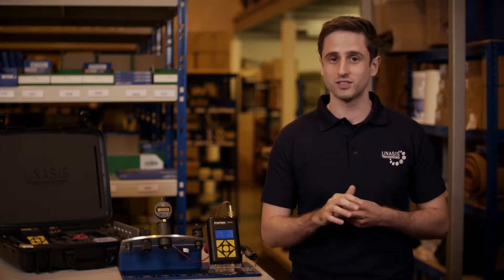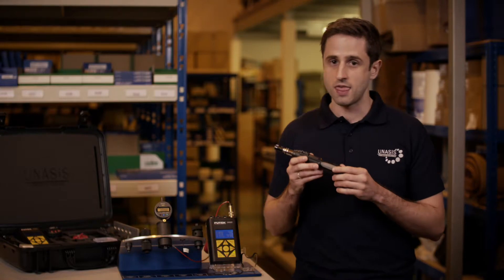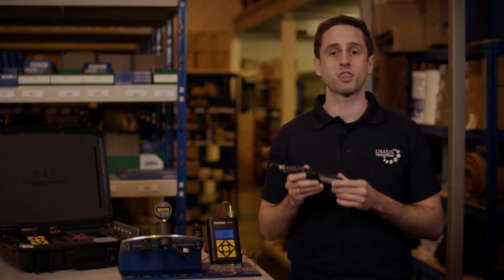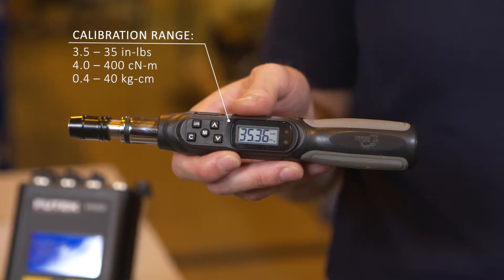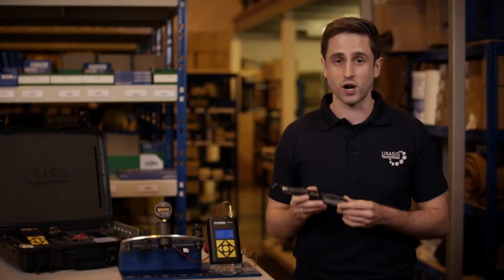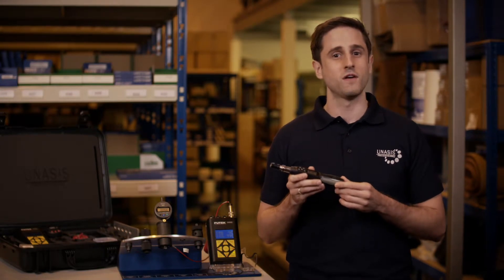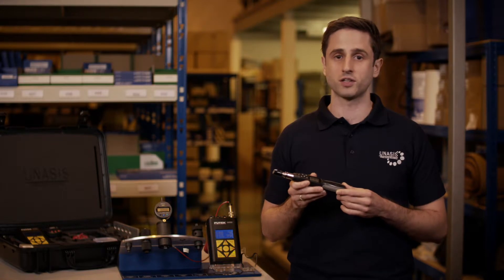The main benefits of this tool are that it's completely portable, accurate, consistent, and easy to use. Within this kit we have the Unasis Digital Torque Wrench. This particular wrench is calibrated between 3.5 and 35 inch-pounds. We also have options for higher and lower torque ratings. The wrench has settings for both tracking torque and peak torque. For this test we'll be using the peak torque setting, which will provide our breakaway torque value.